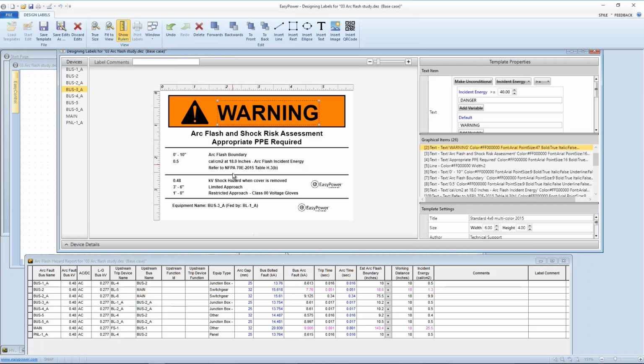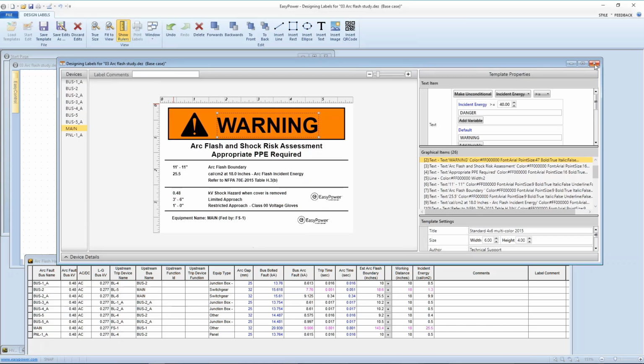So again, all this information can be modified, and as I scroll through the buses, I can see that it pulls up that specific information for that bus, including the upstream feeder breaker that would be used to isolate this bus if we wanted to do so. So all of that's included in an arc flash report, and that's how the tools help me produce the calculations and the collateral material that would be stored or included in my report.